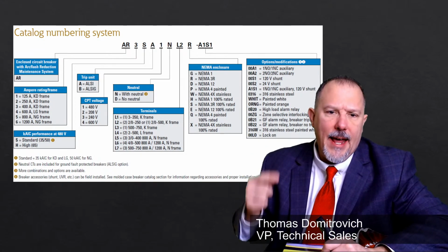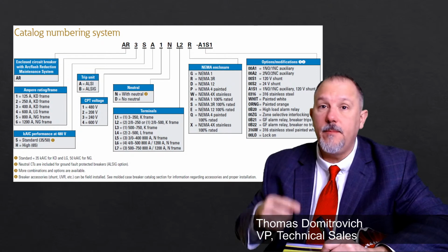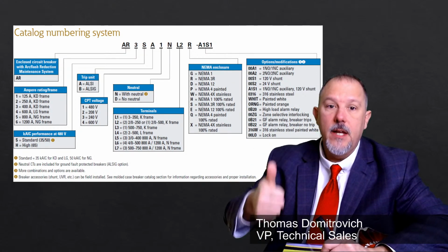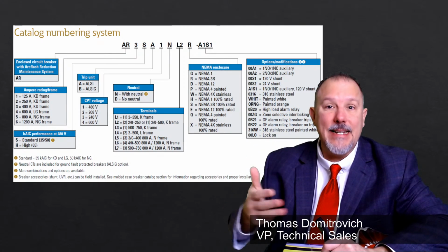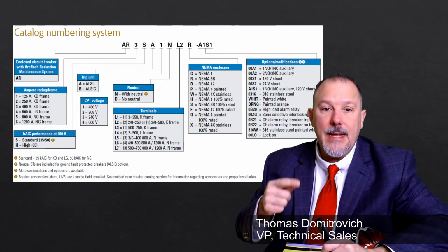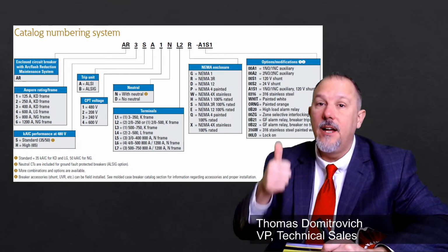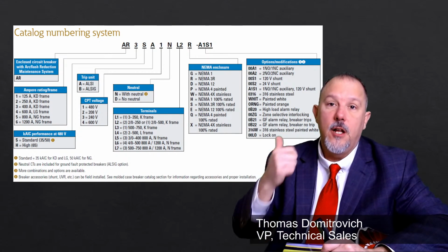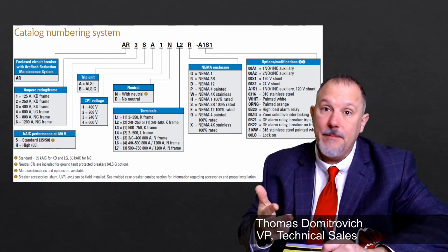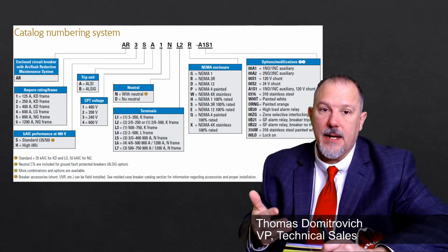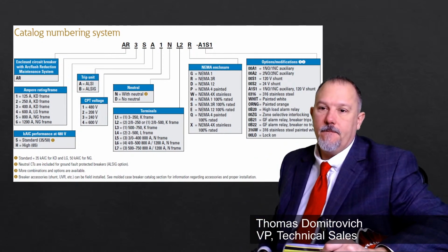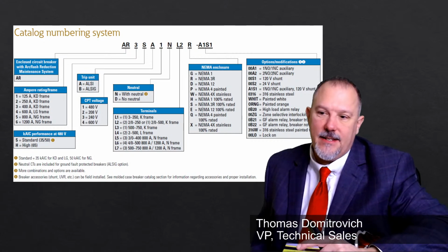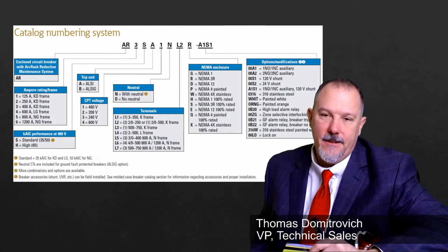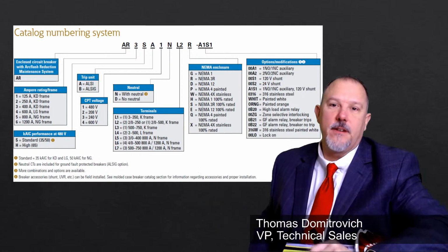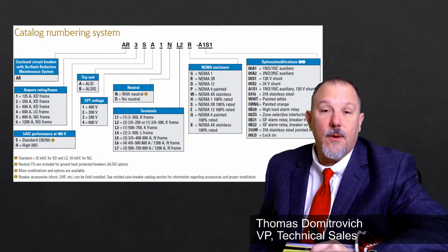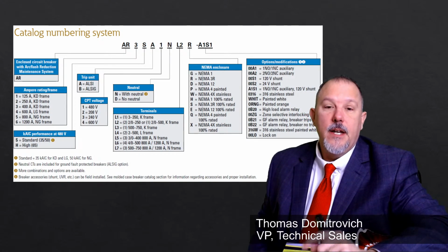The A tells you if it's ALSI, meaning arc flash reduction, long time, short time, and instantaneous. The B tells you it's an ALSIG, arc flash reduction, long time pickup, short time delay, instantaneous pickup. And what do you think the G is? Give you a second to put it in the chat. What do you think the G is? It's not G, your hair smells terrific. Ground fault. All right, it's ground fault.